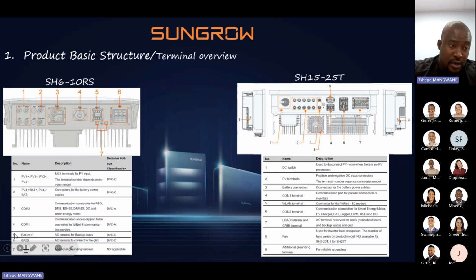Terminal 5, that is our backup port. It's where we connect all our essential loads. And then 6, it's our grid main incomer, your live, neutral, and earth coming from the grid side. Okay, indication 7, it's where we bond our inverter casing with ground. Okay, on the side here is not listed. It's actually our isolator switch for the PV strings. So it's your on and off isolator for the PV.